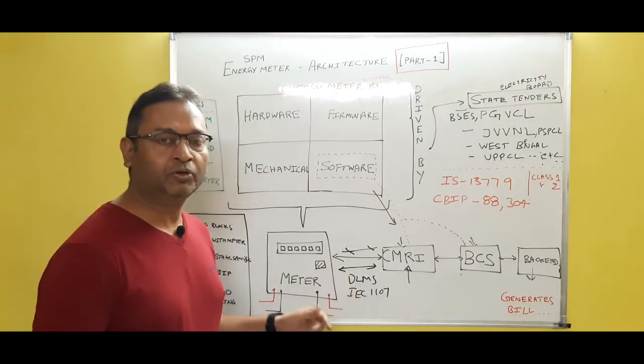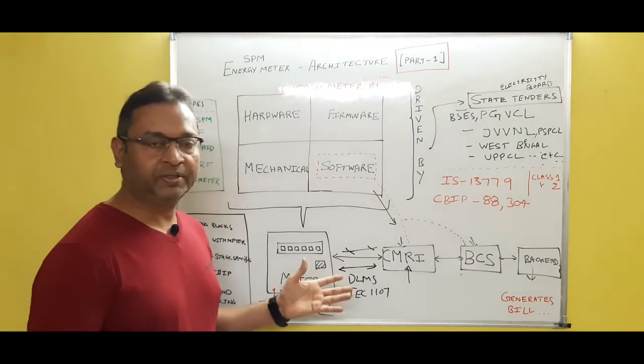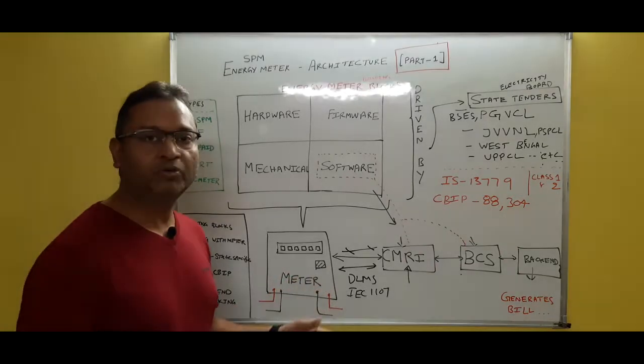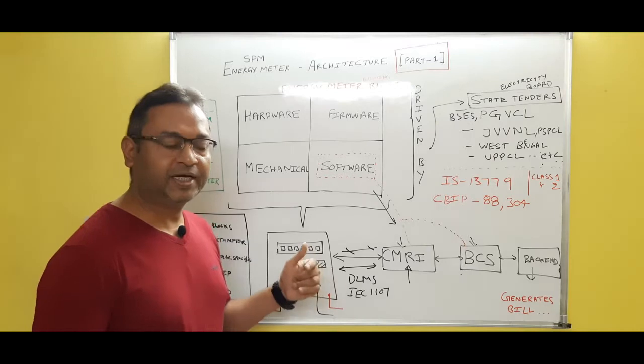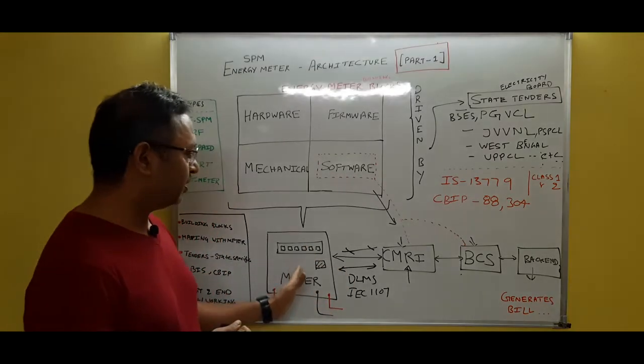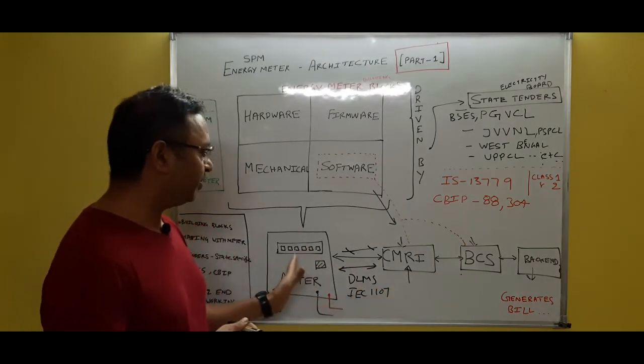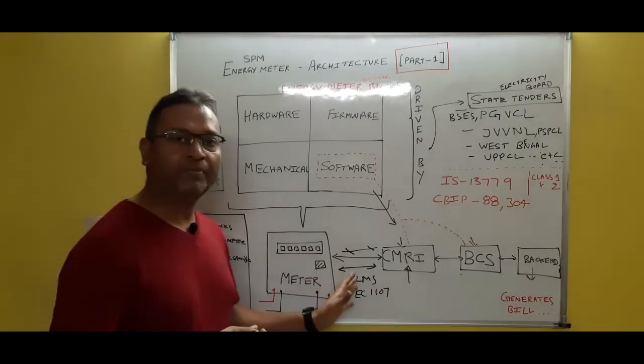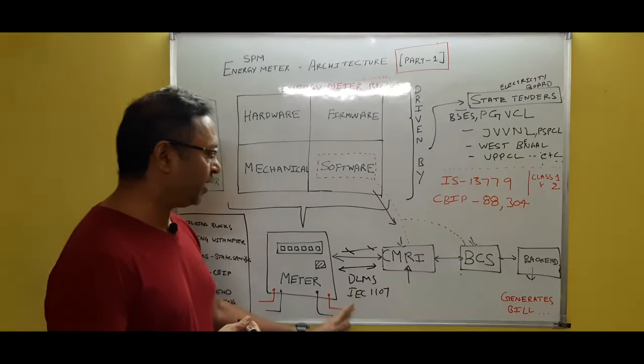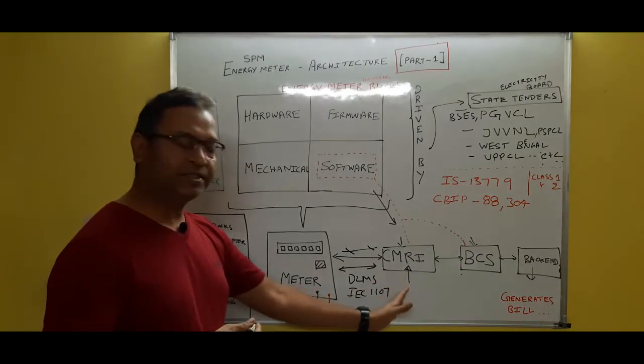So here your meter reader or the meter supervisor guys monthly come with the CMRI equipment. CMRI stands for Common Meter Reader Instrument, and this instrument talks to your meter through optical port or through IR communication or through IRDA communication, or maybe some through wired communication. So these are the physical channels to communicate the CMRI equipment with the meter.